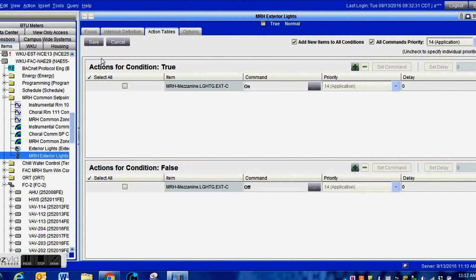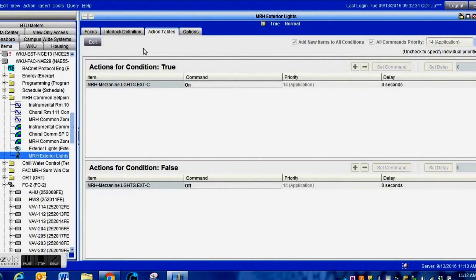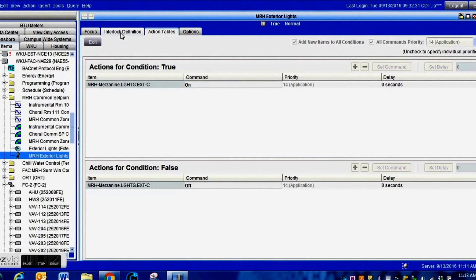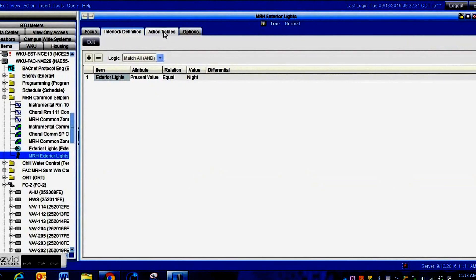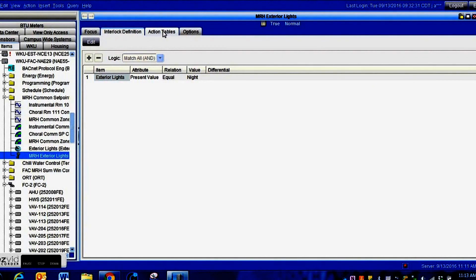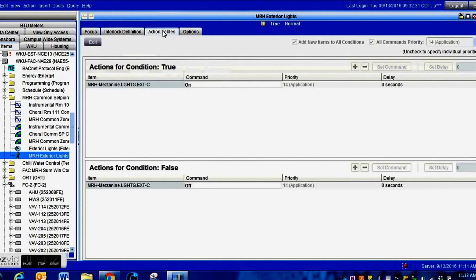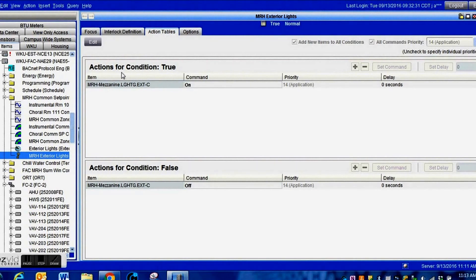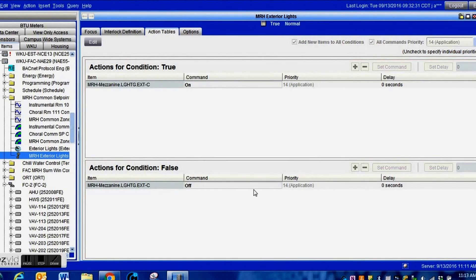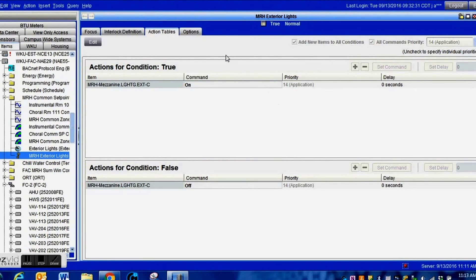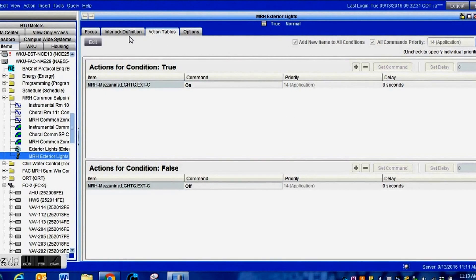One thing I always like to do is change my command priority. That way during troubleshooting it's easier to come back through and find where your command is coming from. If you set all your command priorities for interlocks the same, that is the basic principles of setting up the solar clock. Once the solar clock tells us that it is night, we will then go over to the action tabs. When it is night it is true, it will turn on our command for the lighting. Once it goes to daytime it will then turn the command for the lighting off. This is a very powerful and useful tool and can really help you automate your system.